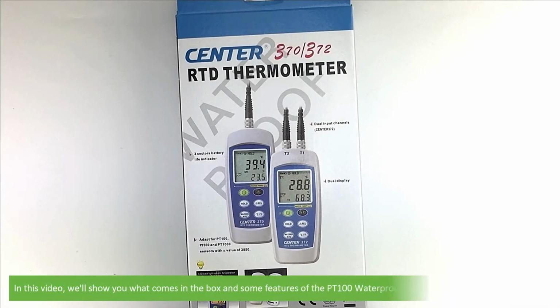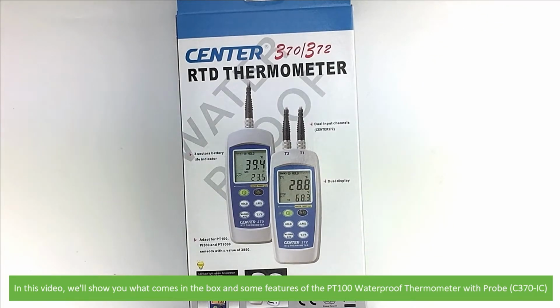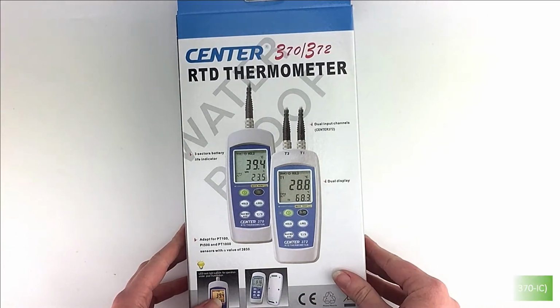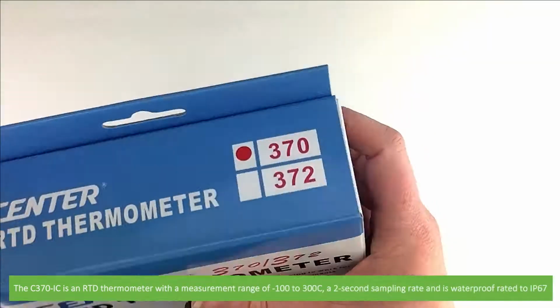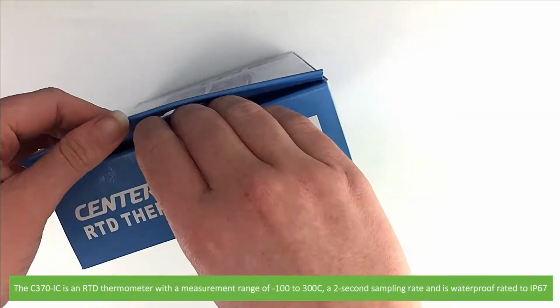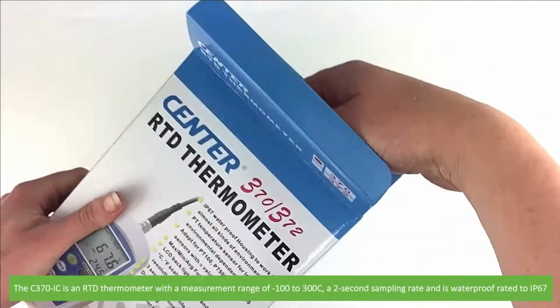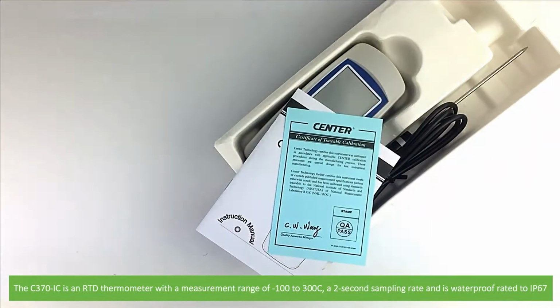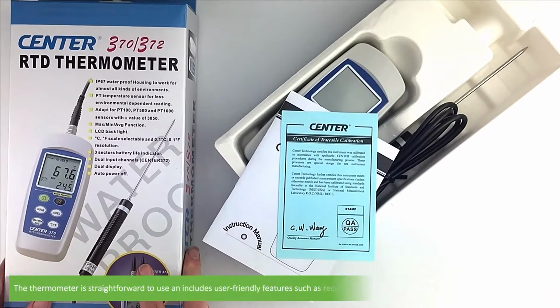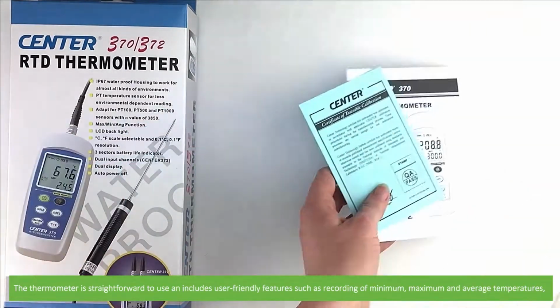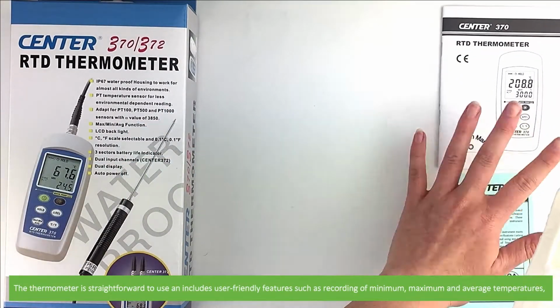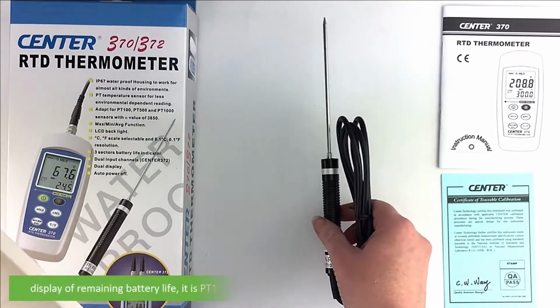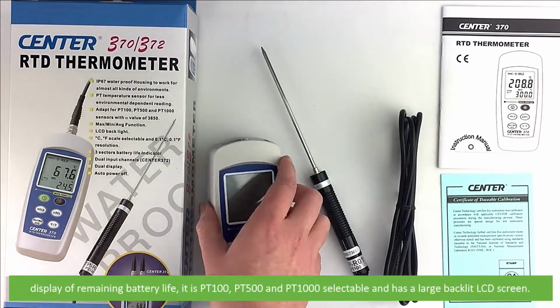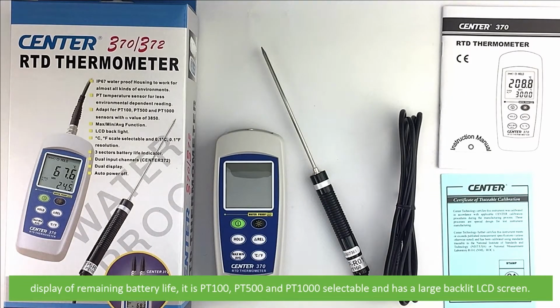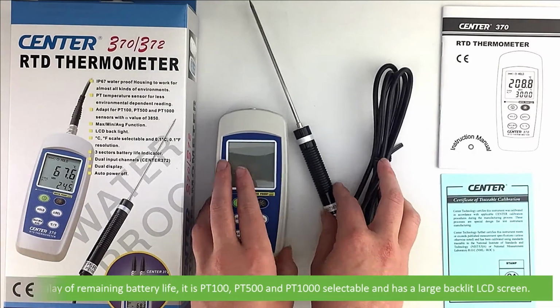In this video we'll show you what comes in the box and some features of the PT100 Waterproof Thermometer with Probe, the C370-IC. The C370-IC is an RTD thermometer with a measurement range of -100 to 300 degrees Celsius. It features a 2-second sampling rate and is waterproof rated to IP67. The thermometer is straightforward to use and includes user-friendly features such as recording of minimum, maximum and average temperatures, display of battery life. It is PT100, PT500 and PT1000 selectable and has a large backlit LCD screen.